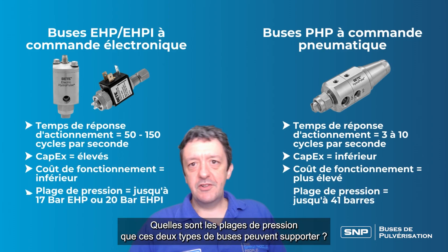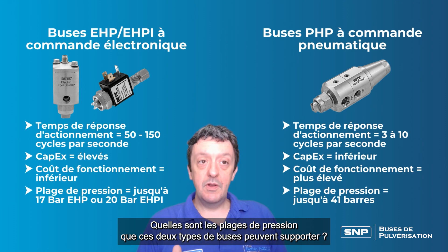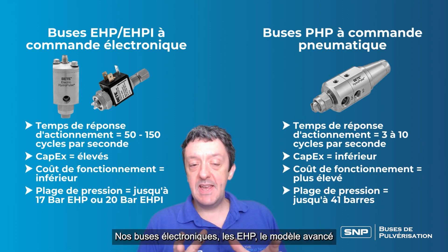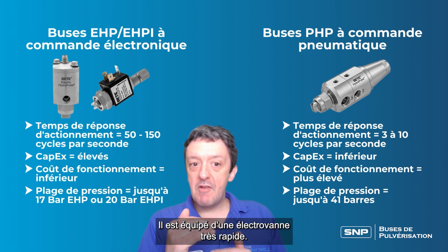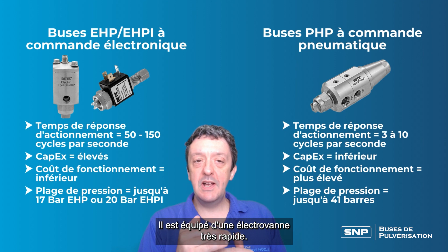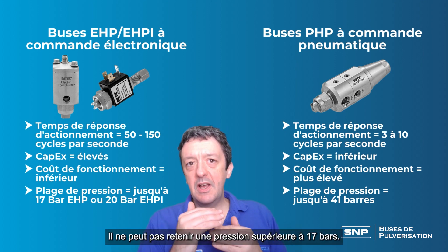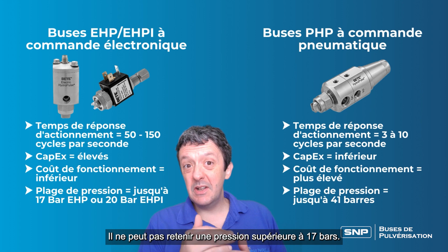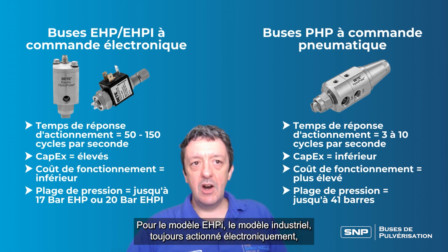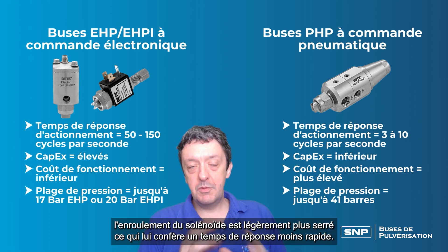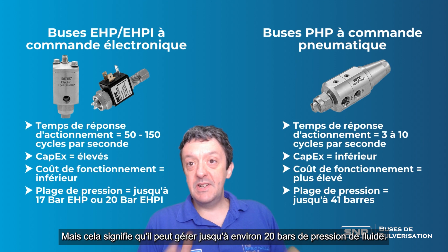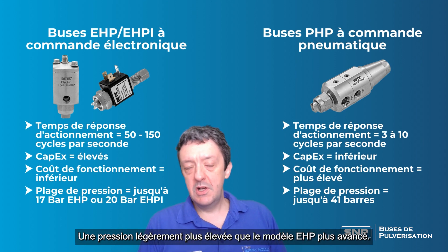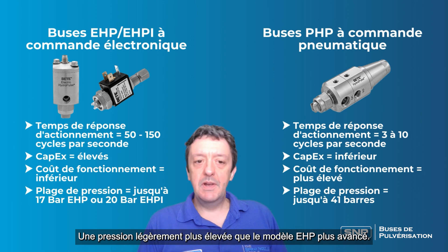Next, let's look at the pressure range — what pressure ranges can these two types of nozzles cope with? Our electronic nozzles, the EHP advanced model, can cope with up to about 17 bar of fluid pressure, with a very rapidly responding solenoid valve. The EHPI, with a less rapid response time, can actually handle up to about 20 bar of fluid pressure, so it's slightly higher pressure than the more advanced EHP model.